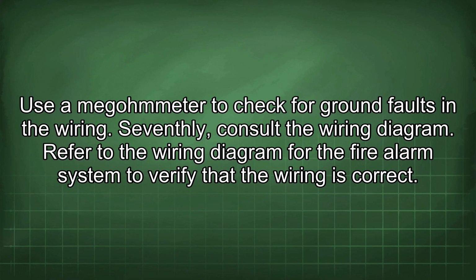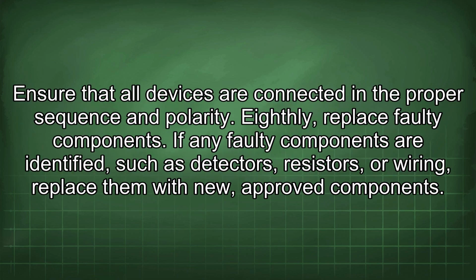Seventhly, consult the wiring diagram. Refer to the wiring diagram for the fire alarm system to verify that the wiring is correct. Ensure that all devices are connected in the proper sequence and polarity. Eighthly, replace faulty components.